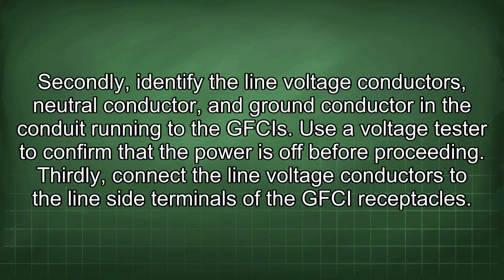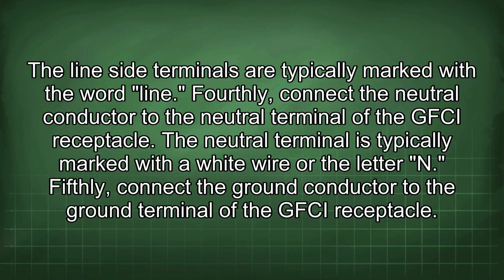Secondly, identify the line voltage conductors, neutral conductor, and ground conductor in the conduit running to the GFCIs. Use a voltage tester to confirm that the power is off before proceeding. Thirdly, connect the line voltage conductors to the line side terminals of the GFCI receptacles. The line side terminals are typically marked with the word line.